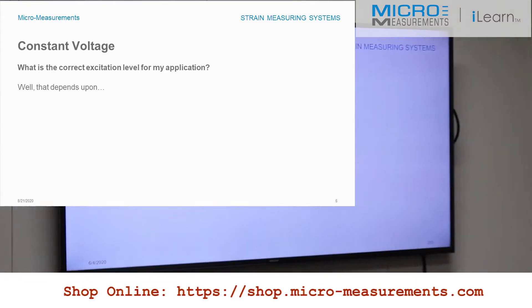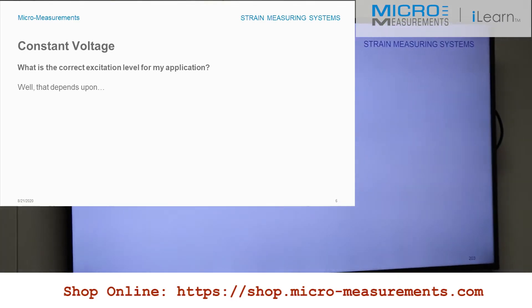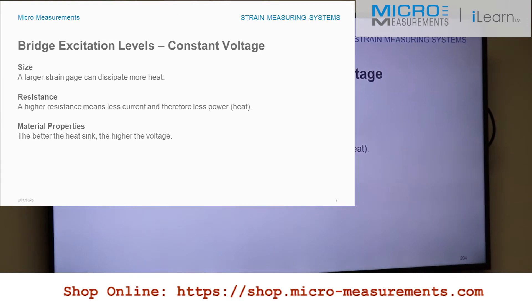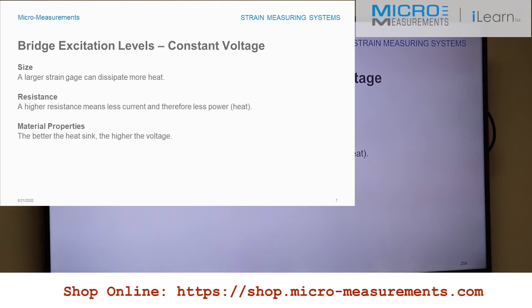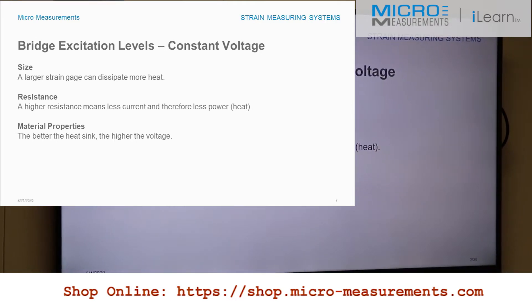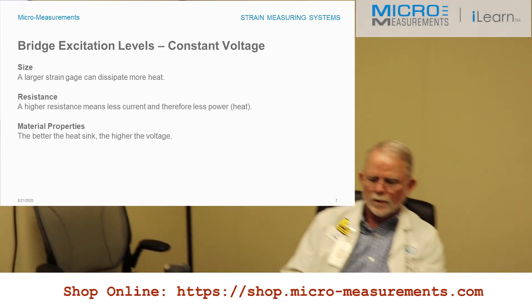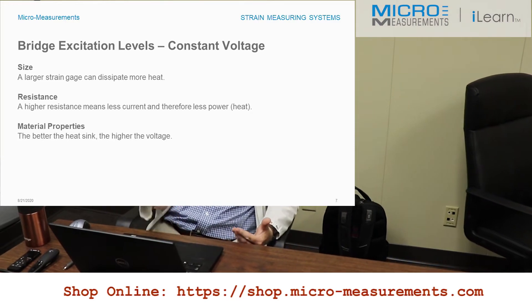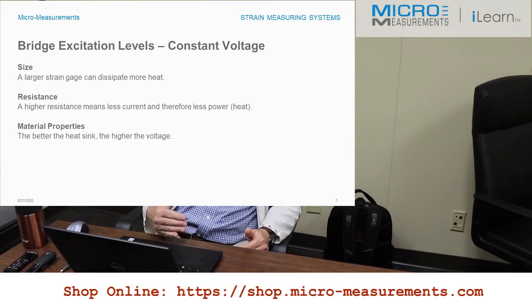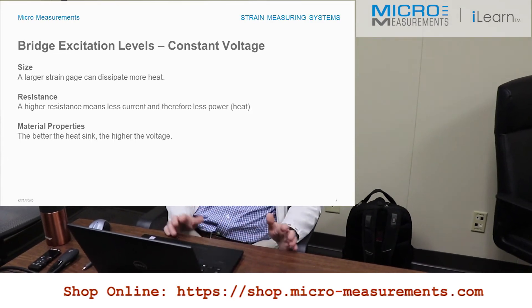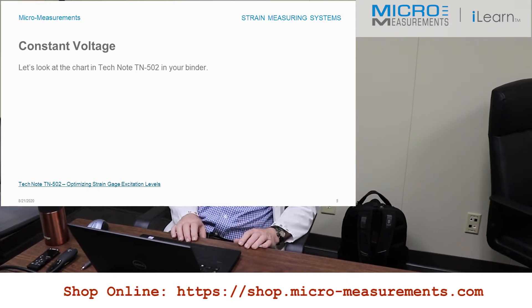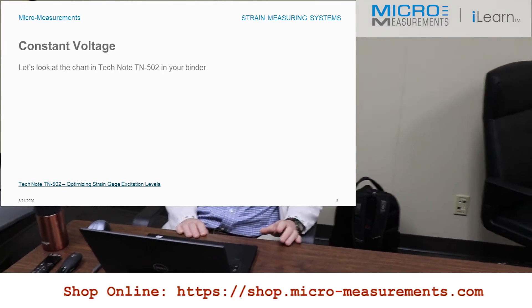What is the excitation level for my application? That depends on a couple of factors. The first one is the size of the strain gauge — it's like a little radiator, and the bigger it is, the more heat it can dissipate from the excitation going through it. When you run excitation through a strain gauge, the current produces heat and that heat must be dissipated. Bigger radiator, better heat dissipation. The next factor is resistance — higher resistance means less heat, so higher resistance is a better situation. Finally, the material properties of the substrate you're bonding to. What kind of heat sink is it? Copper or aluminum are excellent heat sinks. Plastic or glass are very poor heat sinks. The higher the heat sink capability, the more excitation you can put in before you reach a phenomenon called grid self-heating.